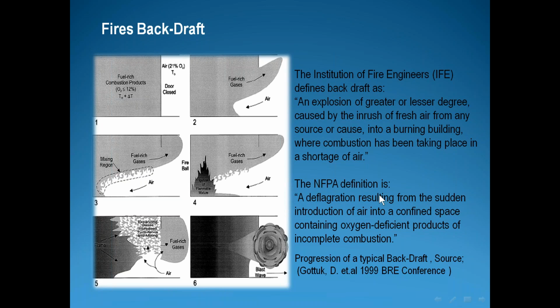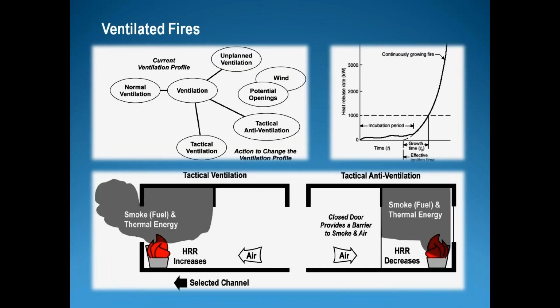And this is the definition stated by the NFPA, the National Fire Protection Association, the association that holds all the research in the United States. Now we go directly to the ventilated fire. This means we go again to the requirements, or how I can judge whether this building needs smoke management or not. If the building is well ventilated, naturally ventilated, or mechanically ventilated with a well-designed ventilation system, I will not be worried about the flashover or backdraft.